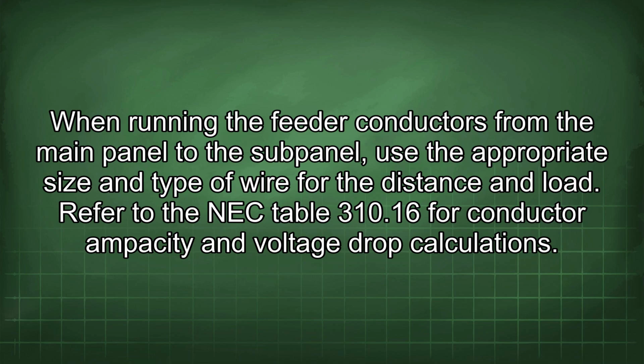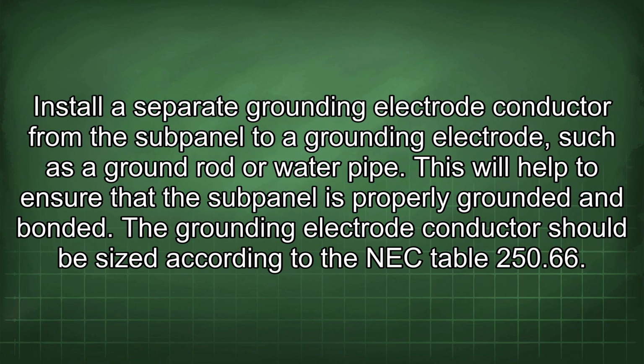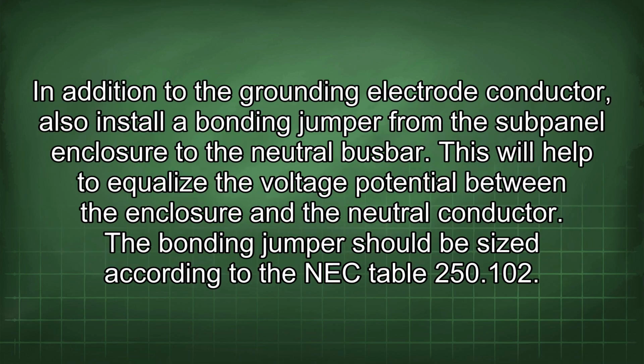Refer to the NEC table 310.16 for conductor ampacity and voltage drop calculations. Install a separate grounding electrode conductor from the subpanel to a grounding electrode, such as a ground rod or water pipe. This will help to ensure that the subpanel is properly grounded and bonded. The grounding electrode conductor should be sized according to the NEC table 250.66. In addition to the grounding electrode conductor, also install a bonding jumper from the subpanel enclosure to the neutral busbar.